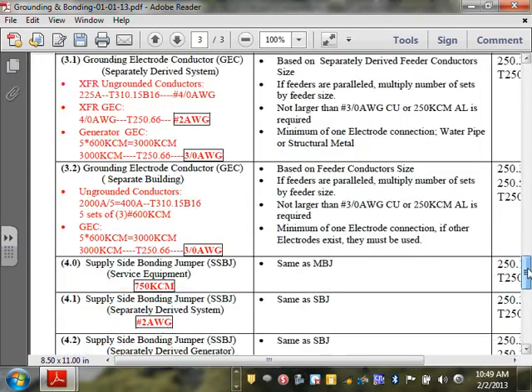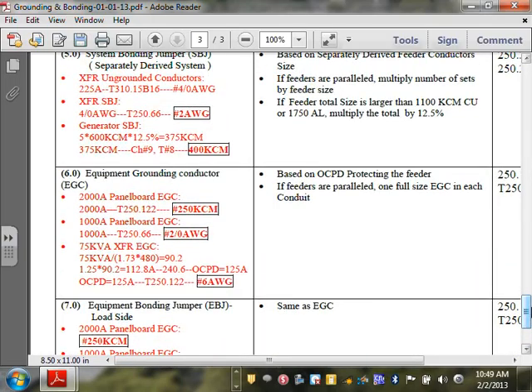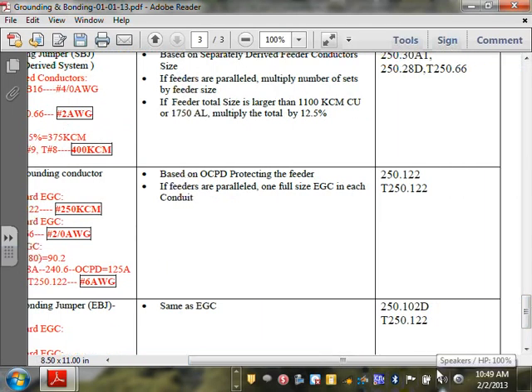So that would be a 2/0. My 1,000 amp panel will be a 2/0 right here. Don't look at the 2,000. We're coming to the 2,000 because number 6 is repeated somewhere else. And don't look at here because we're coming to this area. Just look right now at the 1,000 amp because that's the number 6 that I'm sizing for. And here's the code references for it. Any comments? Any questions about that?